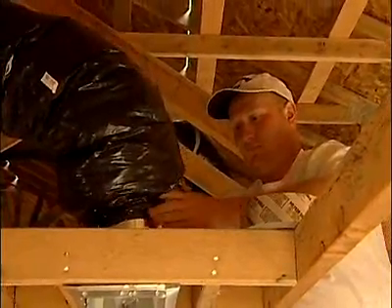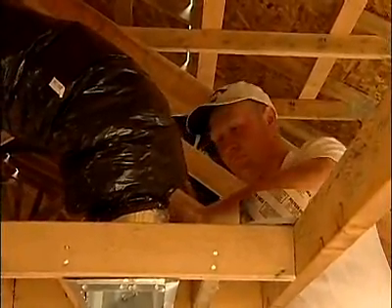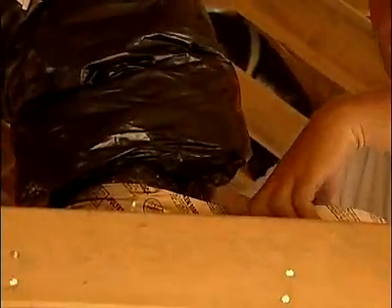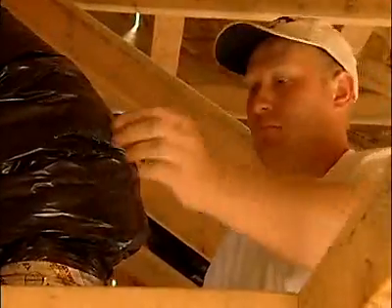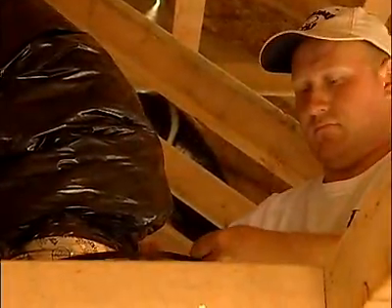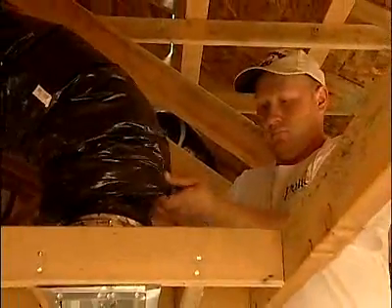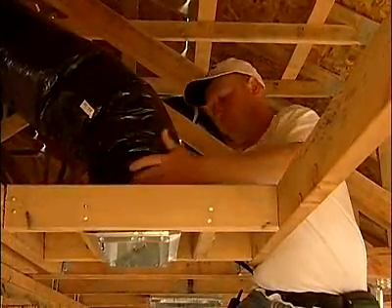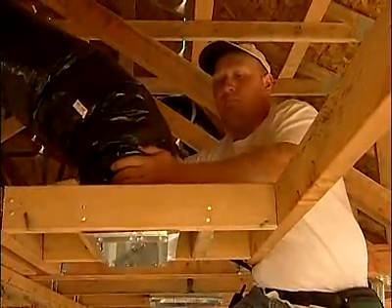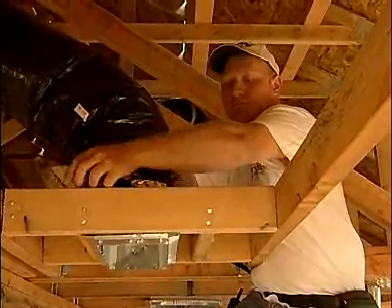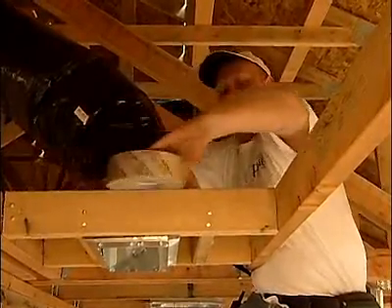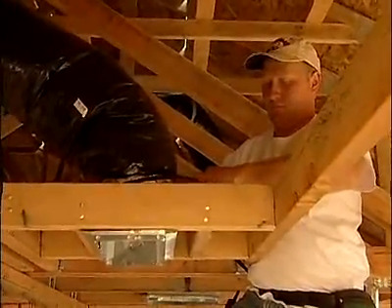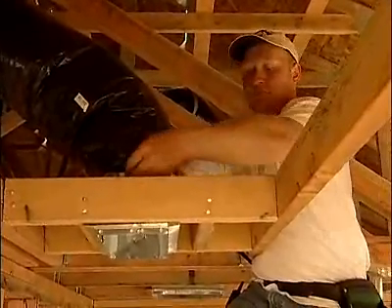Now, codes often require very specific requirements around how these ducts are attached to the boots. Typically what we want to do is to use a drawband and fasten the actual inner liner of the duct to this metal boot, and then we might actually seal that with a UL 181 BFX tape or use a mastic sealant. Some codes actually require that ducts be sealed to no more than 5 or 6% of fan flow. So what that basically means is if we have a 1,200 cubic feet per minute blower system in this, we couldn't have any more than 72 CFM of duct leakage. CFM stands for cubic feet of air per minute.